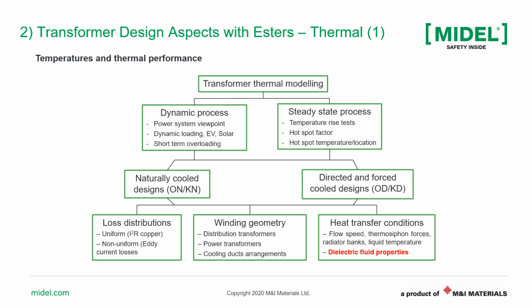The last layer, the bottom ones, are then the contributing factors for the temperature distribution within the transformer. The first one on your left-hand side, you have the loss distribution. These are the uniform losses, I²R, DC losses, and also the non-uniform losses, the eddy current losses within the winding. And then the middle one is the winding geometry. This is the designer. So distribution transformers differ from power transformers. Is it disk type winding or layer type winding? And then all depends on how we arrange our cooling ducts within the transformer. And finally, the right-hand side, we look at the heat transfer conditions. So how fast is our liquid flowing, the flow speed, the thermosiphon forces in natural cooled transformers, how many radiators we have, and what is the typical operating liquid temperature and ambient temperature.